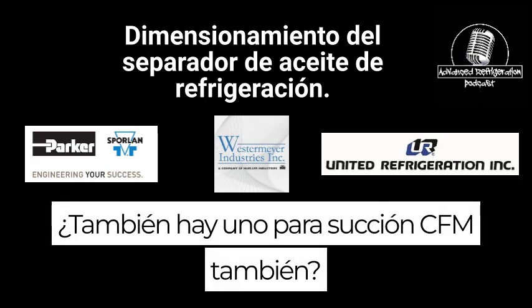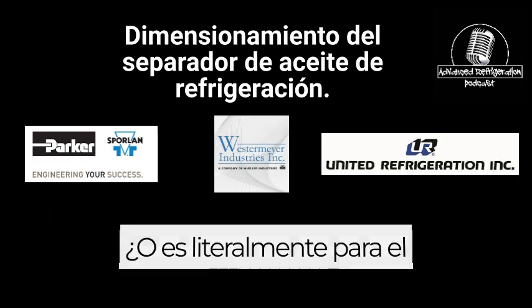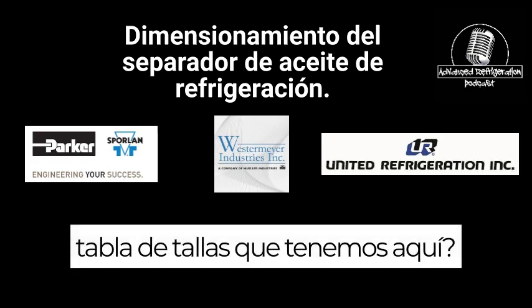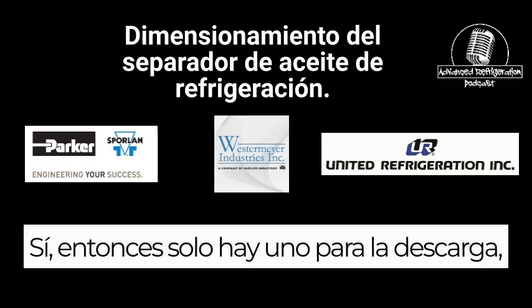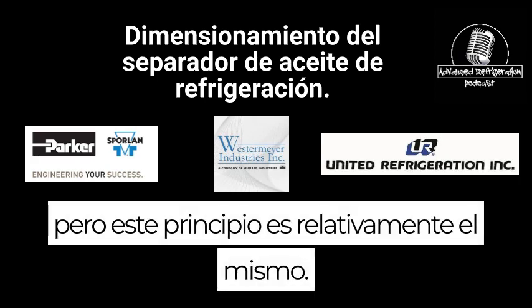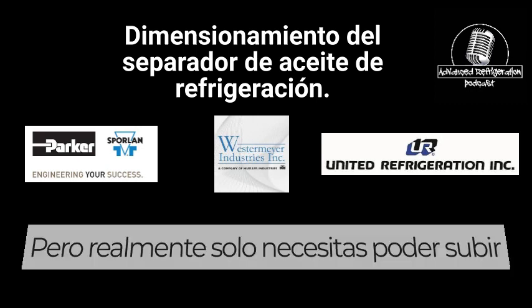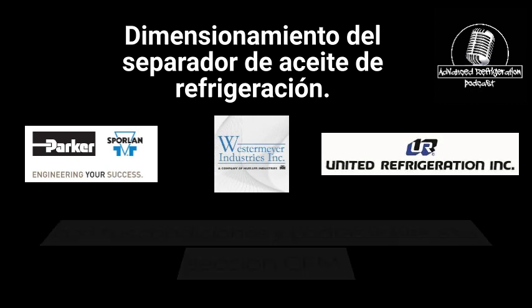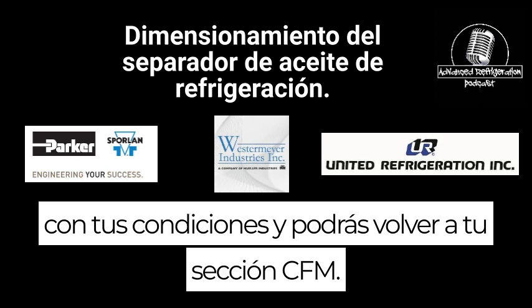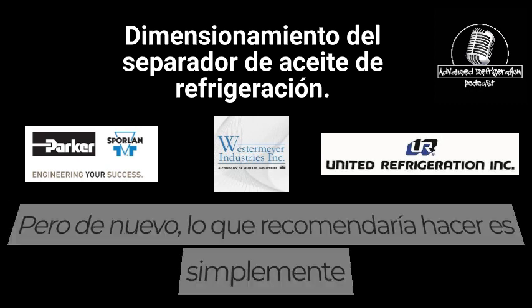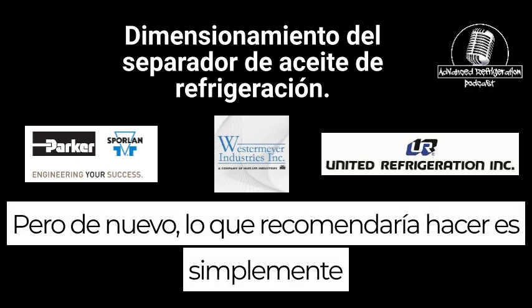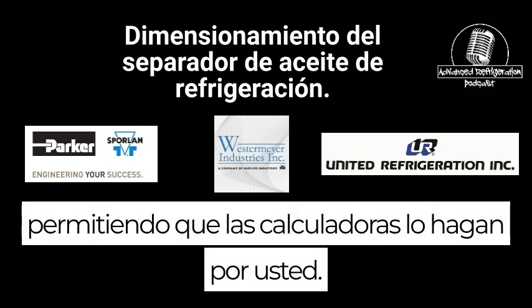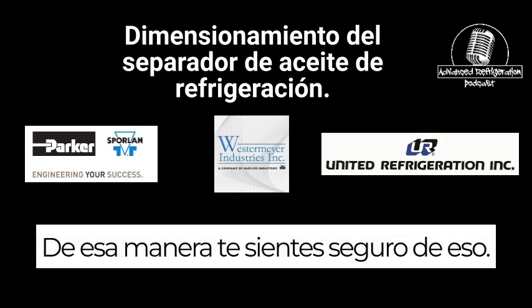Is there also one for suction CFM too, or is it discharge CFM? So you mean for this sizing chart that we have here? Yeah. So there's just one for the discharge, but this principle is relatively the same. But really, you just need to be able to come up with your conditions and you can back into your suction CFM. But again, what I would recommend doing is just allowing the calculators to do it for you. That way you feel confident in that.